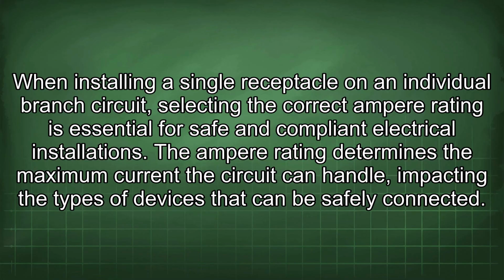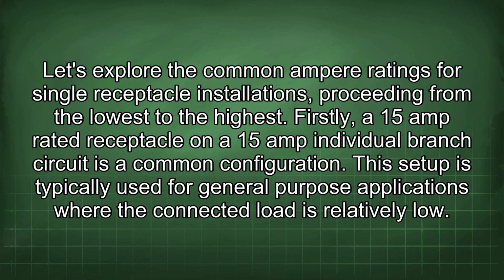When installing a single receptacle on an individual branch circuit, selecting the correct ampere rating is essential for safe and compliant electrical installations. The ampere rating determines the maximum current a circuit can handle, impacting the types of devices that can be safely connected. Let's explore the common ampere ratings for single receptacle installations, proceeding from the lowest to the highest. Firstly, a 15 amp rated receptacle on a 15 amp individual branch circuit is a common configuration.